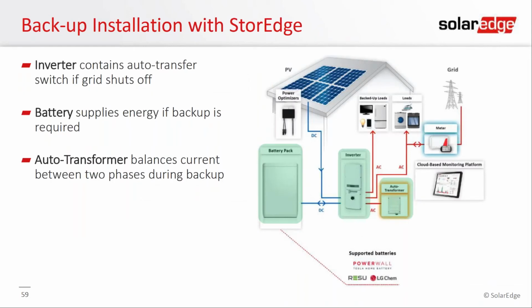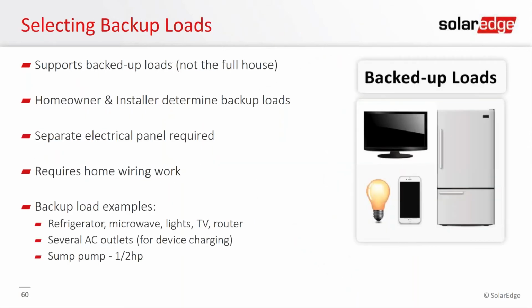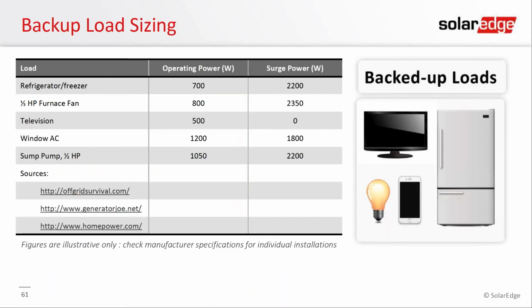Backup power. So as I said before, if you're going to do backup, you're going to need the battery pack, obviously the auto transformer, and then we're going to create a backed up loads panel. So again, this is just a sub panel, super easy to do. For the backup loads, we recommend nothing too big, nothing too taxing. And if we think about the capabilities of the inverter, we can discharge 5 kilowatts continuously, and it's about a 10 kilowatt hour battery. So that means you're only going to get 2 hours if you're discharging the full 5 kW. So what do we recommend? We recommend convenience items. We recommend cost saving items.